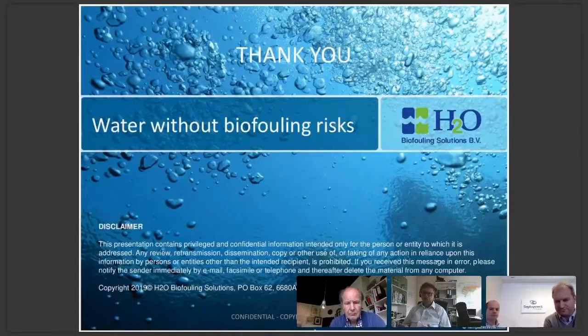Basically, the technologies are based for cooling water systems using surface water, so once through or open recirculation systems, because that's the system where you generally have problems with biofouling. Closed loop cooling water systems can have biofouling issues resulting in MIC, for example, but that's generally caused due to the introduction of bacteria in the system. So that means the closed loop is not 100% a closed system.